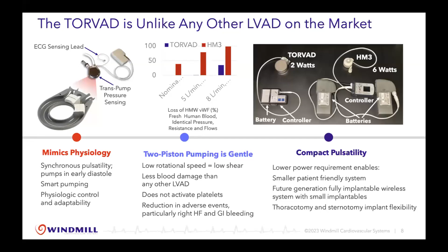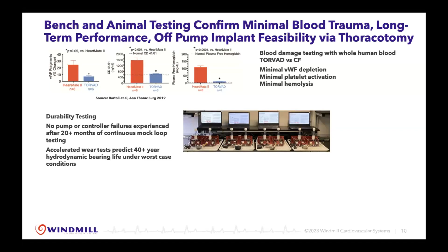But in addition to the blood trauma testing, we've implanted our device in over 50 animals, both acute and chronic animals, the longest up to 60 days. We've had no significant thromboembolic events, no real major problems. In addition, we've done mock loop testing with over 20 months of continuous pump function with varying loads on the pump, and have had no controller failures and no pump failures. We also have done accelerated wear tests that predict the piston mechanism has at least a 40-year hydrodynamic bearing life. So that has been robust.